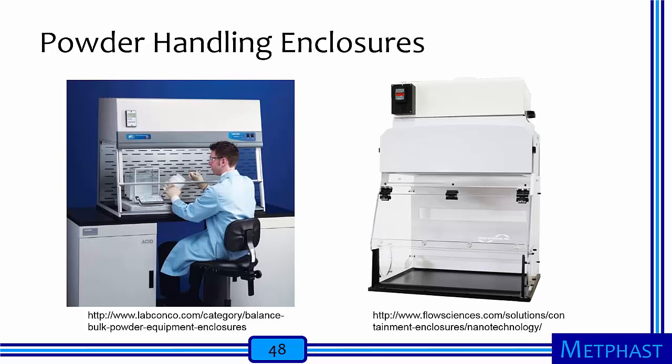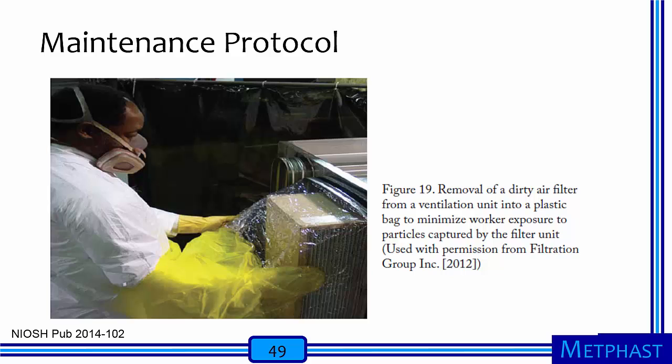Powder handling hoods are specially designed to avoid problems of recirculation typical of constant volume chemical fume hoods. All steps in maintaining production equipment and ventilation equipment must have a protocol in place to limit exposures of maintenance staff. For example, a worker changing the HEPA filter of a ventilation system that services nanomaterial handling operations must follow a protocol involving wearing a respirator, wearing specific protective clothing, and bagging of the HEPA filter.